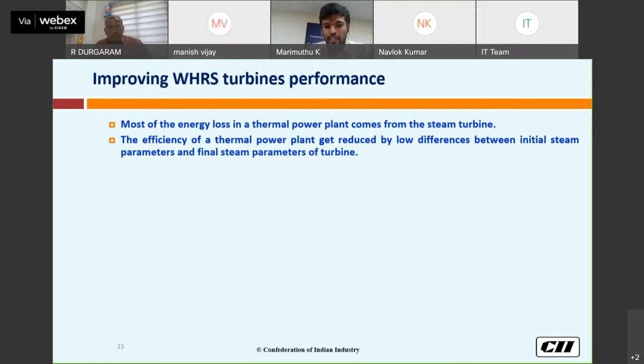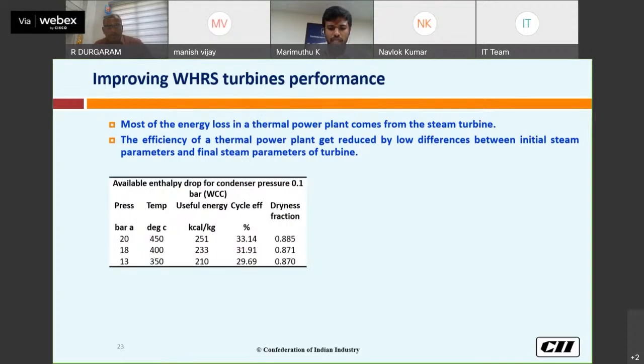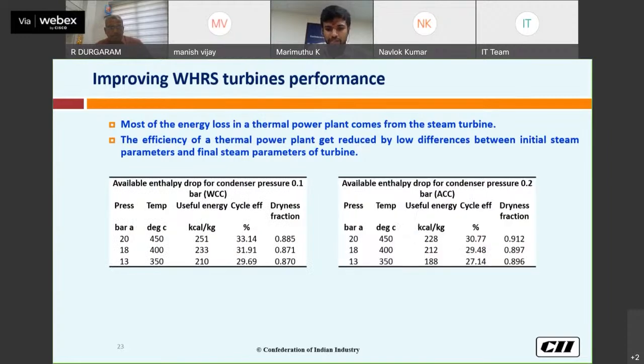So if the enthalpy difference which we are giving between the turbine input and turbine output is less, automatically the efficiency will be less, because if you take a conventional power plant, the efficiency varies between more than 30 to 40. If you go to ultra supercritical, the efficiency will be around 41. But in case of WHR, we will get around 20 to 23 percent. That is due to the less enthalpy difference.